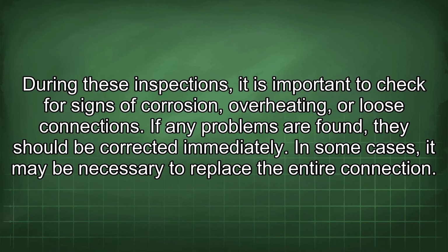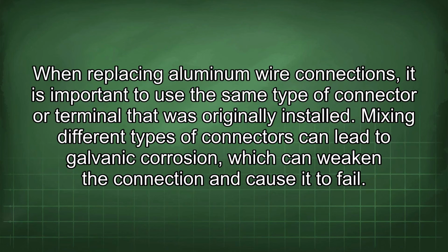If any problems are found, they should be corrected immediately. In some cases, it may be necessary to replace the entire connection. When replacing aluminum wire connections, it is important to use the same type of connector or terminal that was originally installed.